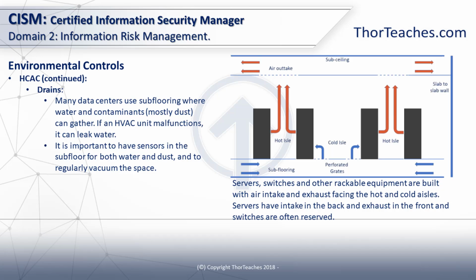Since switches that are racked are used to plug in the networking cables that are located at the backs of the servers, the switches are in reverse. So when you walk through a data center, depending on where you stand, there can be a huge temperature difference. If you're standing in the cold aisle, it can maybe be 50 degrees Fahrenheit or 10 degrees Celsius. And if you're standing in front of the exhaust of a massive server, the temperature can maybe be 105 degrees Fahrenheit or 40 degrees Celsius. That really is how we keep our equipment at optimal operations.